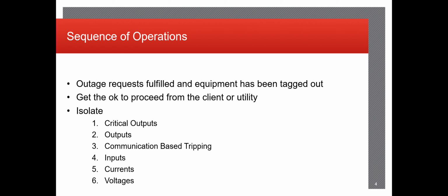And then the last two are your currents and voltages. Now, we specifically do currents first because that is where you will run into the most issues. If you remove the voltages, the relay may not pick up an issue. You always start with your currents and then end with the voltages.